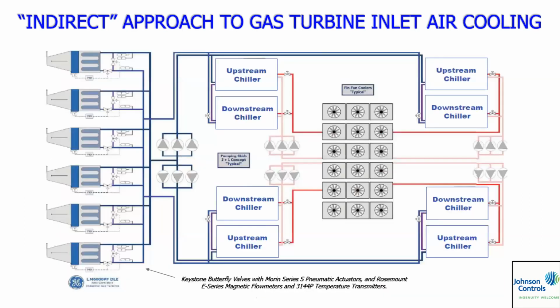And then again, the flow concept: remember the evaporators are in series. The condensers, which are in red, are in parallel. So you see the fan coolers. And again, we had 2 pumps doing the load, 1 standby, so a 2+1 concept for each set of chillers. And the beauty of that is, if we wanted to have the structural steel, we could have stacked them, set them on top of each other, but that's going to take a hell of a lot of structural steel and cranes and things like that. So we could have reduced the footprint.